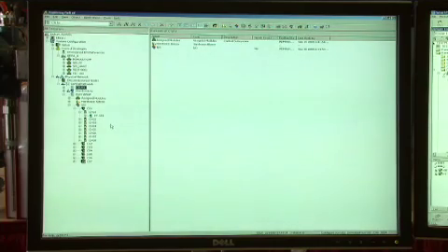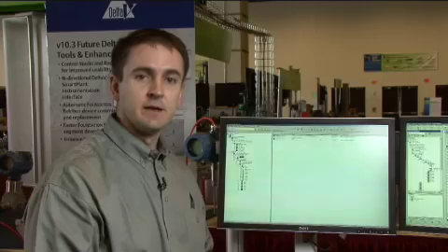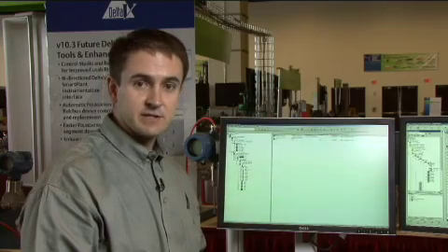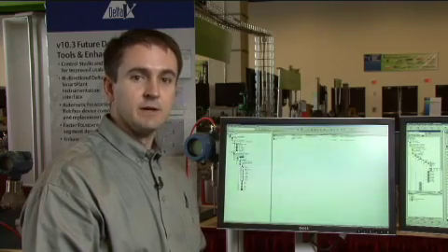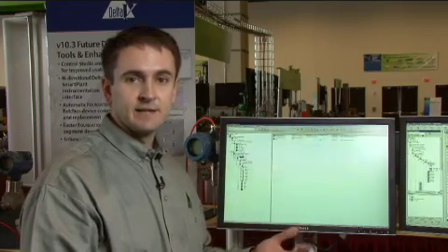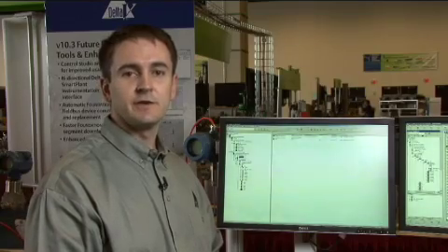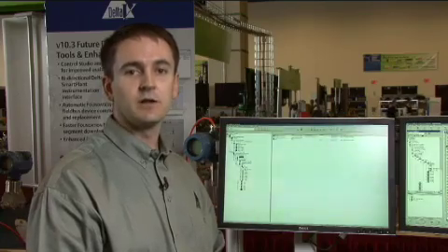Here within the Explorer application, I can see that my node has been created from the data that was configured within SPI. All of my I/O cards and associated channel configuration and instrument configuration is now present within the DeltaV system. This has saved the DeltaV configuration engineer many hours of configuration time. So basically we're taking the data that's been entered into SPI and reusing that data to create DeltaV configuration. This configuration data transfer process improves data handover consistency and quality.